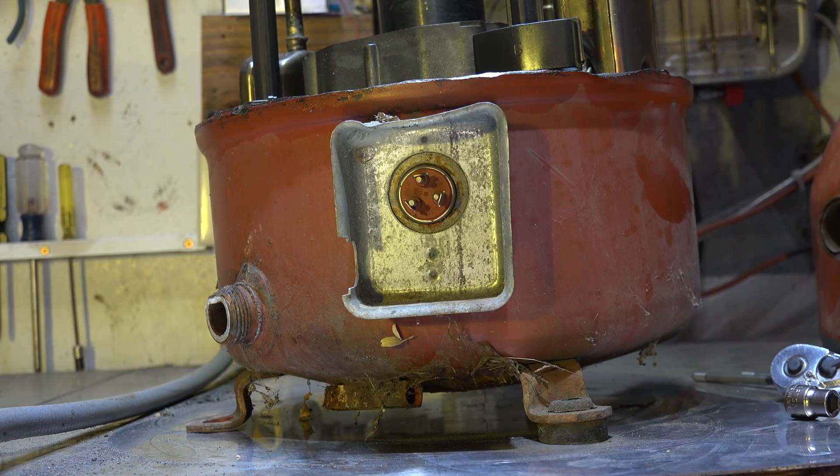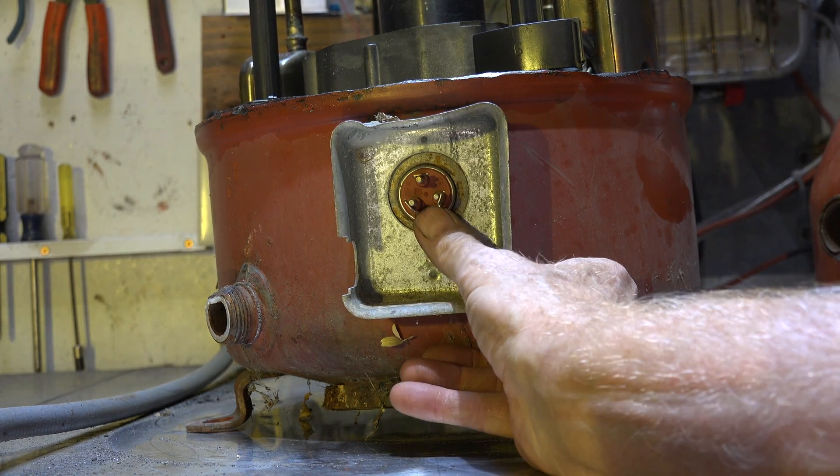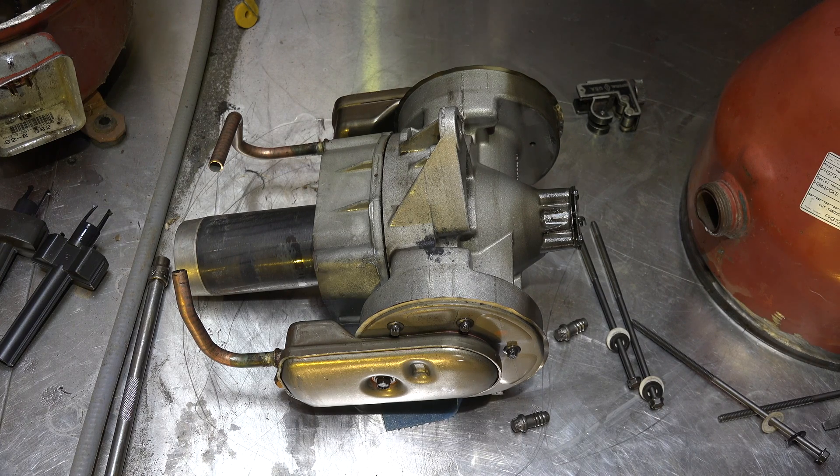Here are the connections on the outside. There's actually a ceramic button inside there and it's kind of rubbery on the outside. I don't get a lot of leaks out of these things. When I first got into this business there was a lot of talk about leaks around these, but the only time I usually find leaks is when the motor shorts out and burns those terminals completely off, blowing a hole right through — and that's obviously a leak you can't fix anyway.